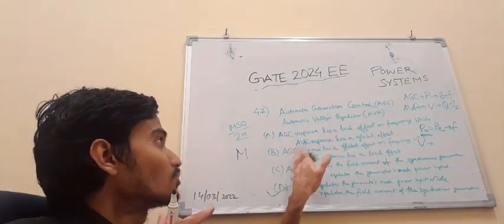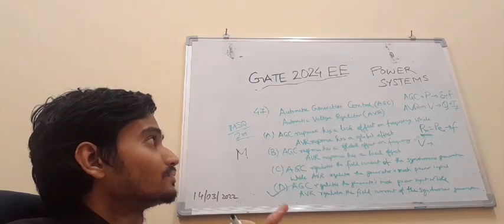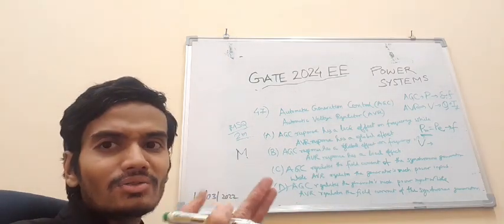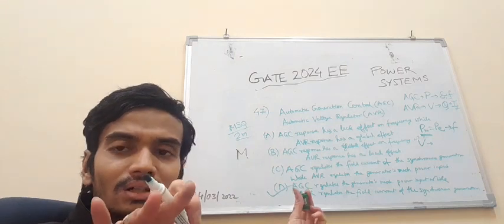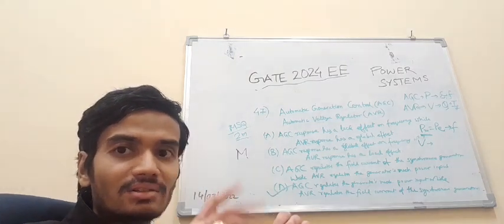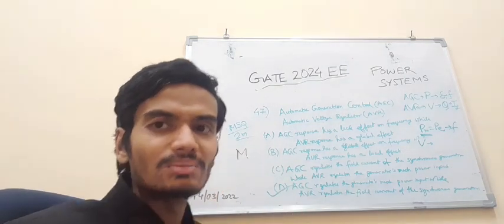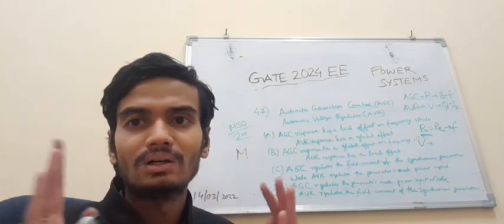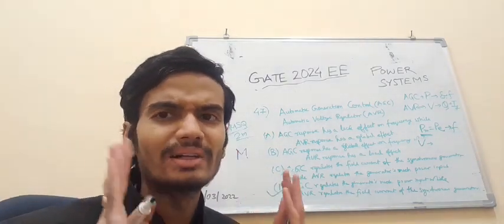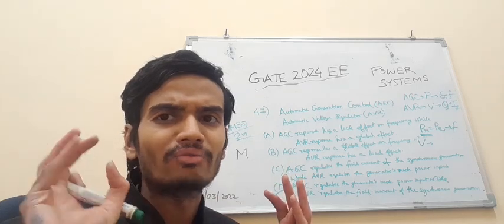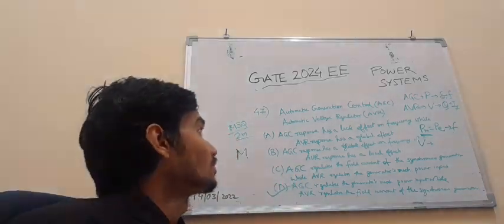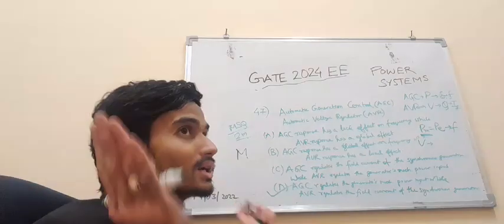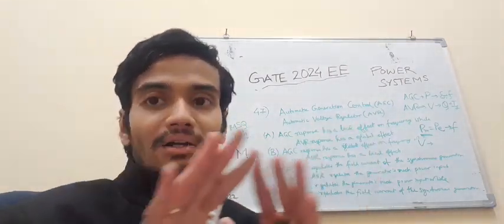While AGC regulates the frequency of the power system. Frequency of the power system, as we know, will be common for all the buses and all the generators. Throughout the power system, the droop or the frequency deviation will be very small, restricted to 0.5% is allowed. So AGC will have a global response. The frequency is common to the entire power system.